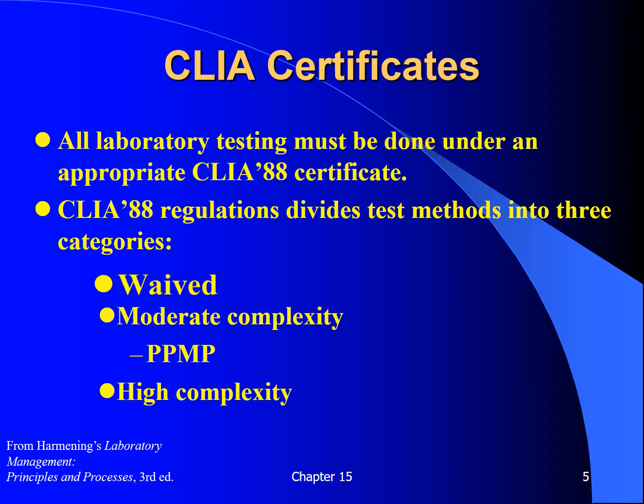If a site develops its own test procedure or chooses to modify an existing FDA-approved procedure, which includes not following the manufacturer's directions, the test automatically falls into the high complexity category and is subject to CLIA's most stringent requirements.